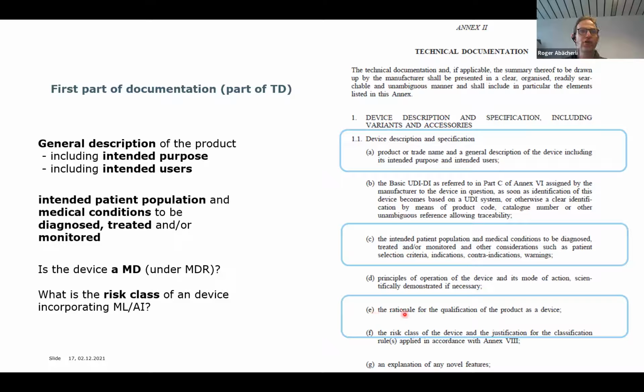Then you have to do a rationale for the qualification of the product as a device. That means whether your medical device is actually a medical device according to those regulations. And following that, you do the so-called risk classification of the device. There is an Annex 8, which has rules to show you what risk class your device becomes.